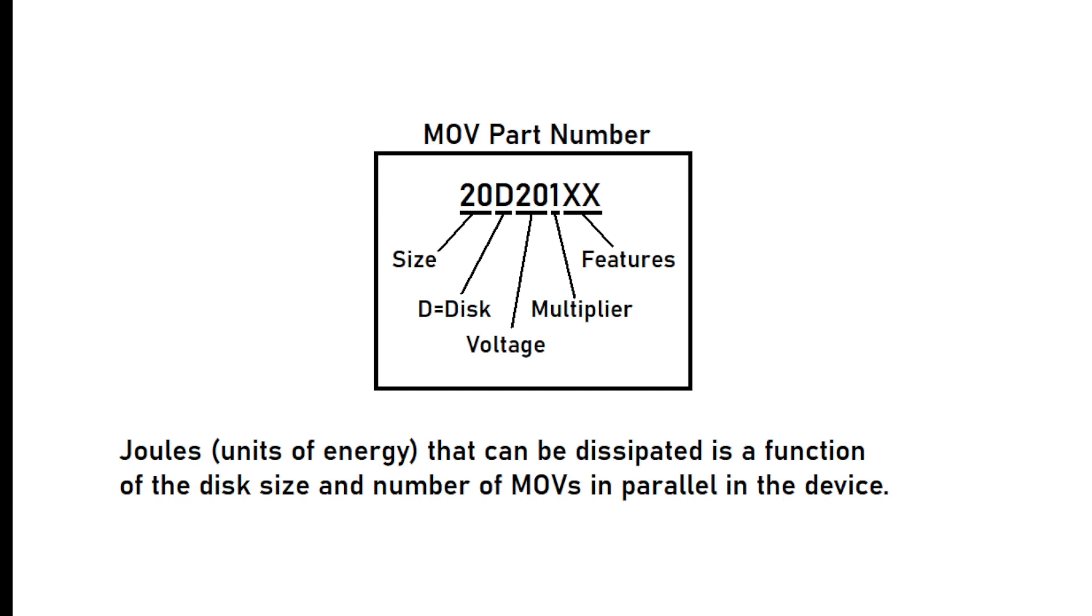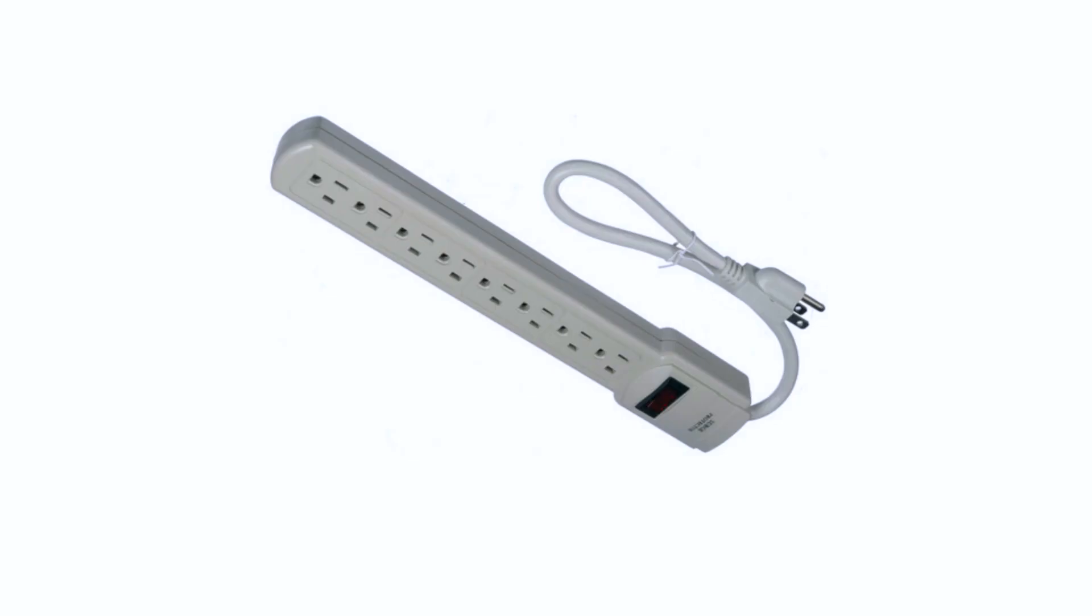Unfortunately, MOVs can wear out over time, which is why I call them sacrificial. When MOVs fail, they can overheat. Therefore, some kind of protection circuitry is desired to take the MOVs out of the circuit when they fail. From a historical perspective, the home-style surge suppressor strips, when the MOVs failed, would sometimes catch fire.